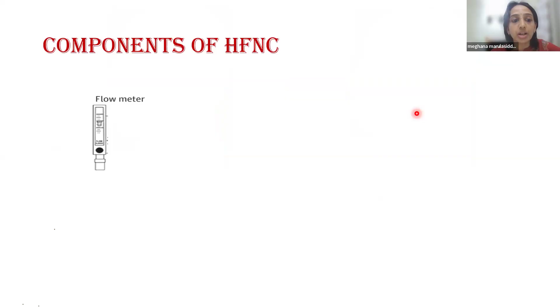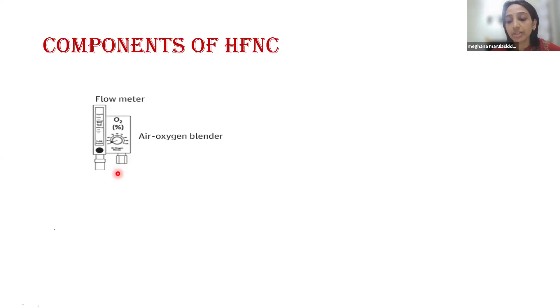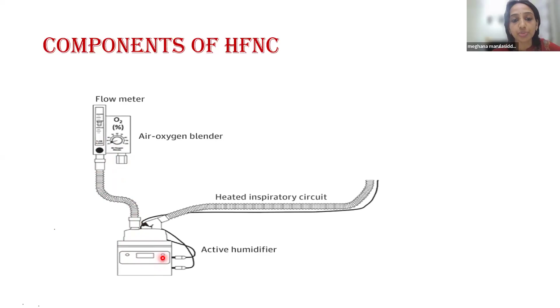Now let us look at the components of the high flow nasal oxygen system. The high flow nasal oxygen system consists of, first, a flow meter. Now this is the oxygen flow meter. It may or may not have an air oxygen blender. This flow meter and the air oxygen blender need to be connected to our oxygen and air pipeline source. Thereafter, there is a tubing that connects the air and the oxygen, and it connects it to the humidifier. This humidifier here sits on a heating plate. Then the gases from here are carried by this inspiratory circuit and go into the patient interface, that is the nasal cannula. This inspiratory circuit here is heated. Now this needs to be heated to compensate for heat loss along the tubing and to prevent condensation.